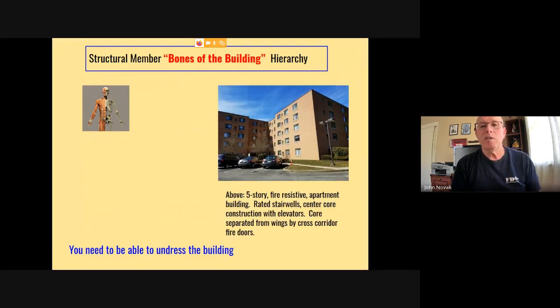The picture I just presented is a fire resistant building in my response area. It's a 5-story apartment building, right? It has rated stairwells, meaning the stairwells have at least a 2-hour fire resistance rating. It's an area of refuge. You can get into the stairwell, it'll take you outside. It is a safe area. It's also an area where the fire department is going to launch an attack using a standpipe system. This building also has center core construction, elevators. It's separated by wings. Fire doors separate the wings into fire areas using cross corridor fire doors.